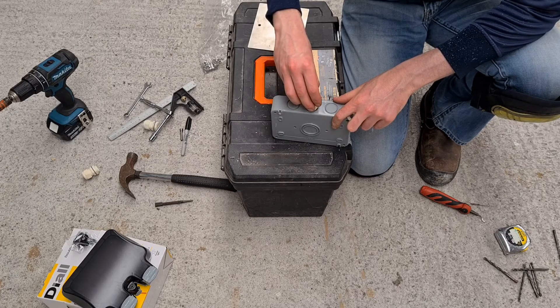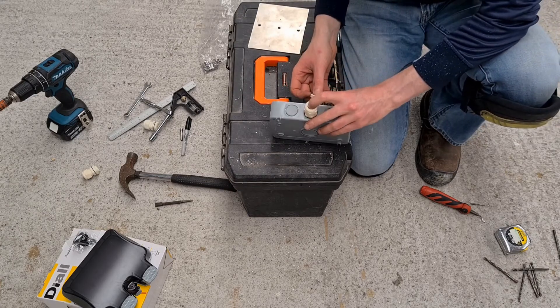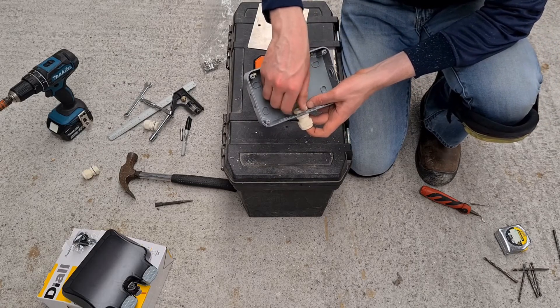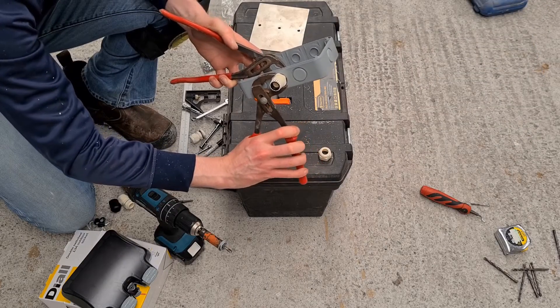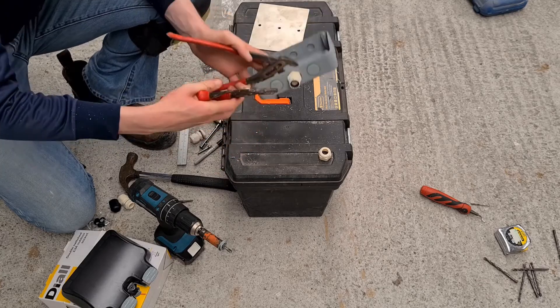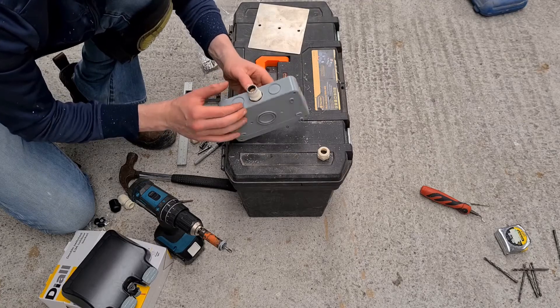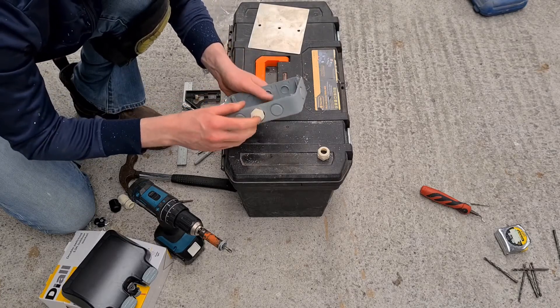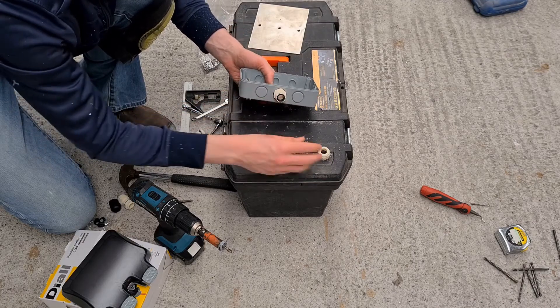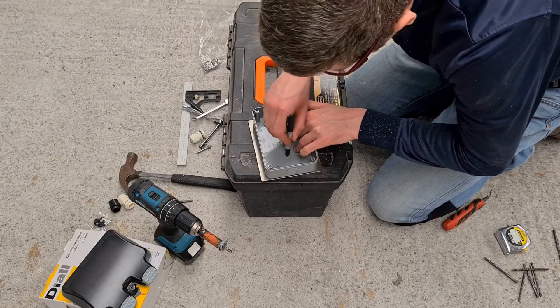Insert a 20mm gland into the surface box hole and tighten the gland with pliers. The gland secures the cable to the surface box and prevents water from entering. Make sure the inner gland nut is tight and check that the gland core doesn't swivel. When the cable is inserted into the gland and the cable nut is tightened, the entire gland can swivel, making it difficult to secure the cable. That's why it's important that the inner gland nut is tight to prevent the core of the gland from moving around.